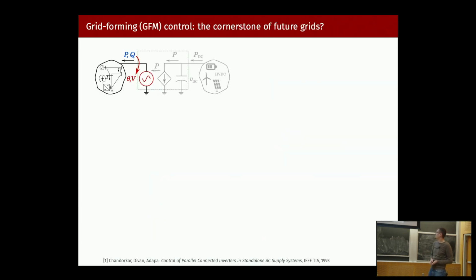The counterpart to this that you'd typically find in literature is the so-called grid forming control. This traces back to papers in the 90s and was rediscovered as its own research field maybe 4 or 5 years ago. The idea here is completely opposite: let me control the AC terminal of a power converter to do something nice for the system, and let me just assume that whatever is feeding the inverter can keep up and produce whatever power I need—which is equally unrealistic unless you put a massive battery there.